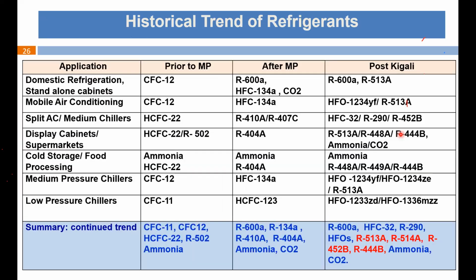So in a nutshell, if I consider prior to the Montreal Protocol, these are the historical trends of refrigerant. For domestic refrigerators, we used R12. Mobile air conditioning means the air conditioners used in movable vehicles. Split ACs used R22. Display cabinets used R22 and R502. Cold storage used R22 and ammonia. Medium pressure chillers used R12, and R11 for low pressure chillers. So prior to the Montreal Protocol, these refrigerants were used worldwide.